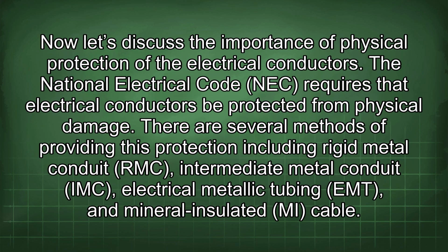Now let's discuss the importance of physical protection of the electrical conductors. The National Electrical Code (NEC) requires that electrical conductors be protected from physical damage. There are several methods of providing this protection, including rigid metal conduit (RMC), intermediate metal conduit (IMC), electrical metallic tubing (EMT), and mineral insulated MI cable.